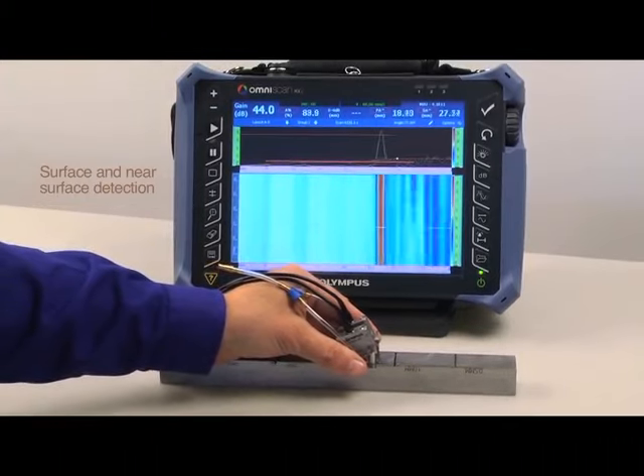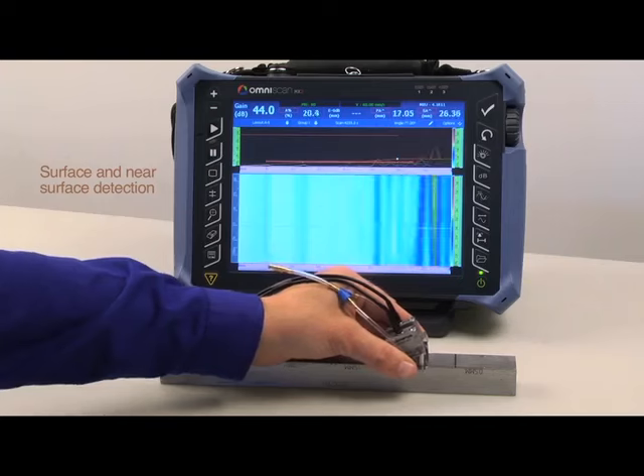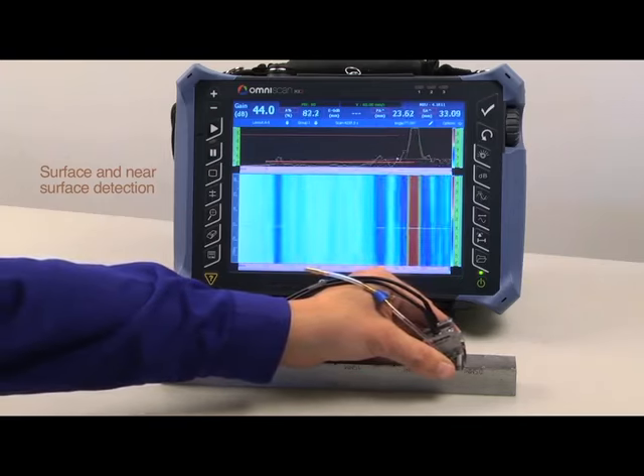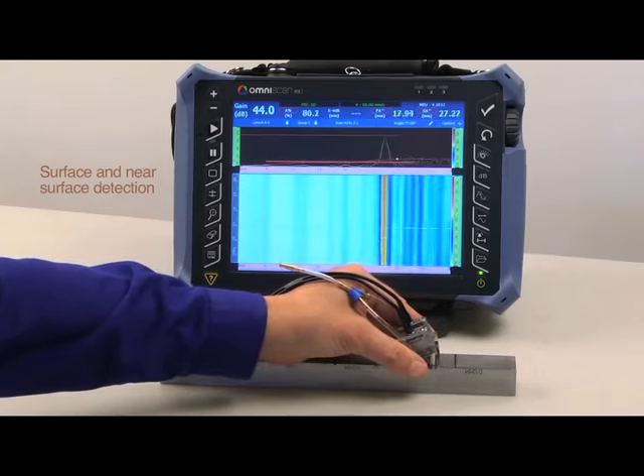In this example, using a wedge optimized for surface and near-surface detection, a 70 to 85 degree longitudinal wave S-scan is focused at 20 millimeters in front of the wedge face where shear wave pulse echo full V-skipping is not possible for shallow and surface connected flaw detection.